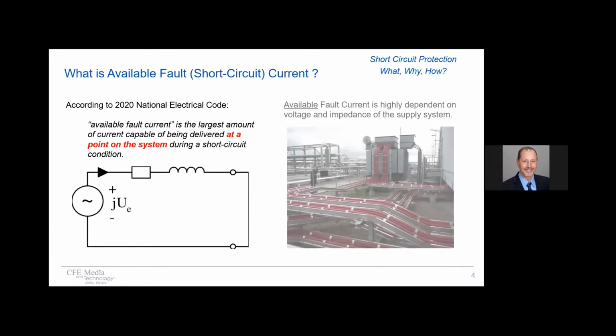As you can imagine, there are many different points on the system, and available fault current at any given point is highly dependent on the voltage and the impedance of the supply system. So if you were connected, for example, directly at the output of a transformer, you would have very high fault current. And if you were connected at some point down the line where you have cable impedance, etc., your available fault current at that point would be much less. Okay, that helps us understand what fault current is, but why do we care?